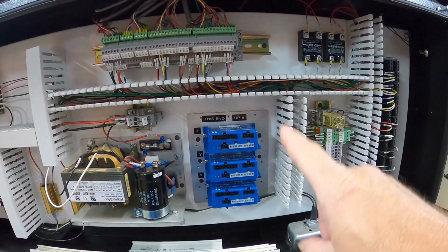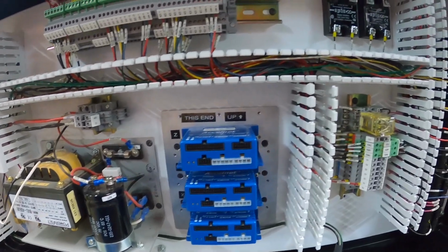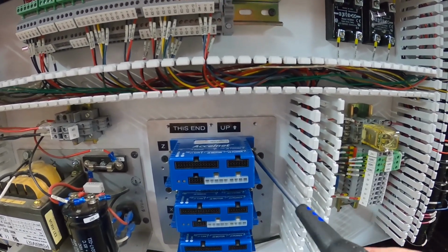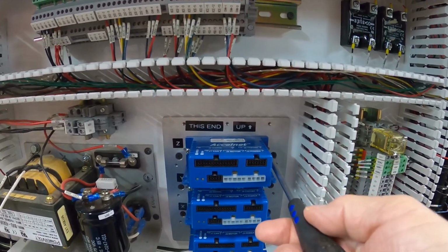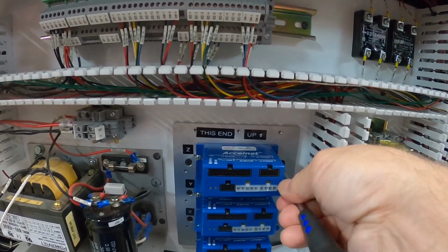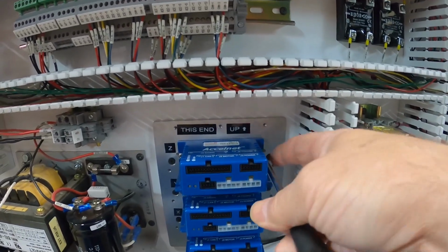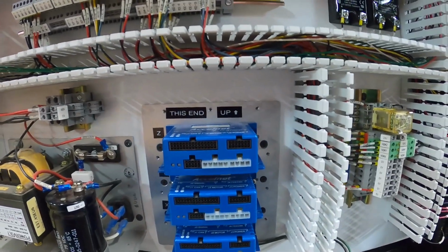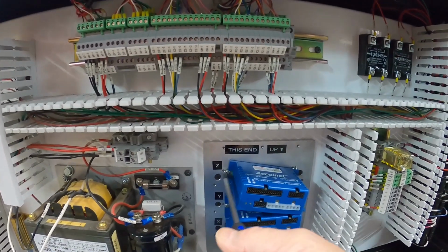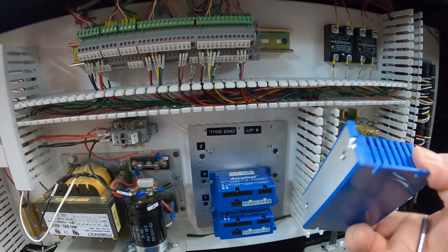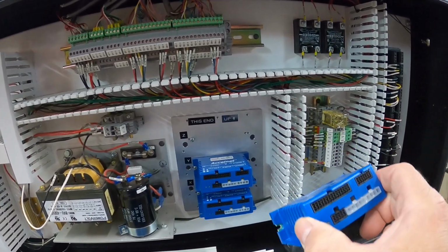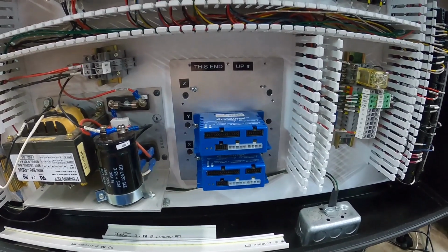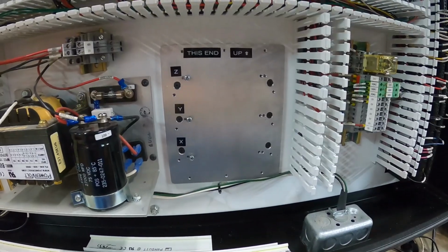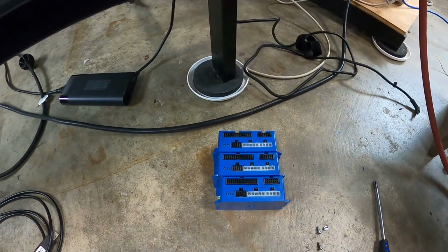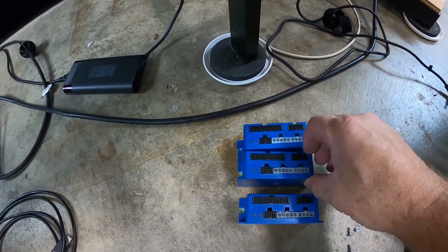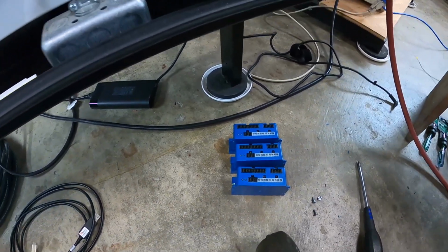So we've got all of the wiring removed from this machine, and then to take a drive out, you basically take a Phillips screwdriver and take one screw out from one side. Let's see how I do this with one hand. Then you can just loosen this screw, and the drive essentially falls out. So there's your drive. And you just repeat that to take the other 2 drives out. There we have all the drives removed. Now, when you take the drives out, make sure you label them somehow, so you keep them in order of how they were in the machine, because they're programmed differently.